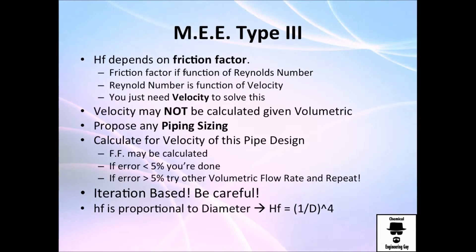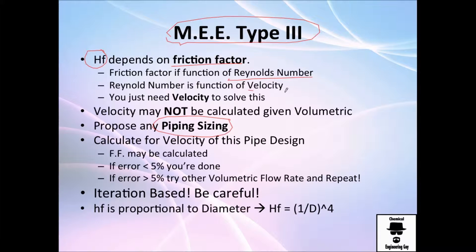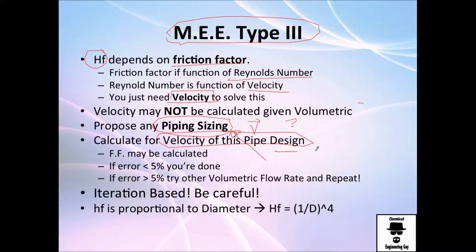What happens if we have no pipe sizing? This will be typical problem type number 3. Recall that friction loss depends on the friction factor, the friction factor depends on Reynolds number, Reynolds depends on velocity, and velocity depends on the size of the pipe. We will not have volumetric flow rate and therefore we will not have a velocity. We need to propose several pipe sizes, calculate the velocity for each, then calculate the left side and make sure it equals the right side. If it is not, recalculate everything; if it is right, you're done.